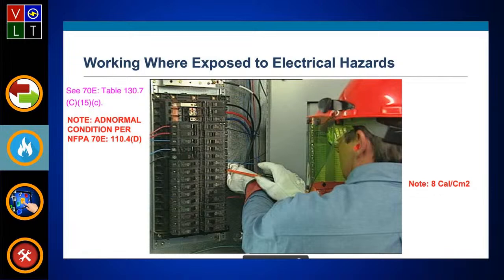No, we're going to look at that next. That would be considered in 110.4D as normal operation. And if it was circuit breakers, you'd go to NFPA 70B as referenced from 70E 200.1. As long as you maintain everything properly in that panel board at 480, 277, or whatever voltage range—240, 208, whatever it may be—you can even switch those with the cover on. But you have to meet normal operation per 110.4D.